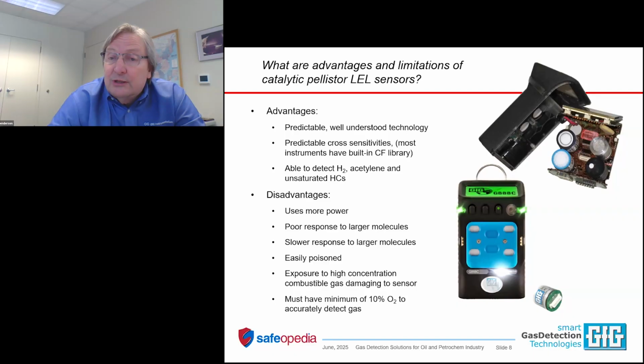Disadvantages are it uses a little more power than the other kinds of sensors. It has a poor response to larger molecules, a slower response to larger molecules. Very importantly, you can poison it by exposure to certain sensor inhibitors or poisons. The top of the list of sensor poisoners would be silicone, vapors that contain silicones. It has a requirement for the presence of oxygen in order to detect gas. If you have less than 10% oxygen in the monitored atmosphere, then your readings may not be fully accurate.